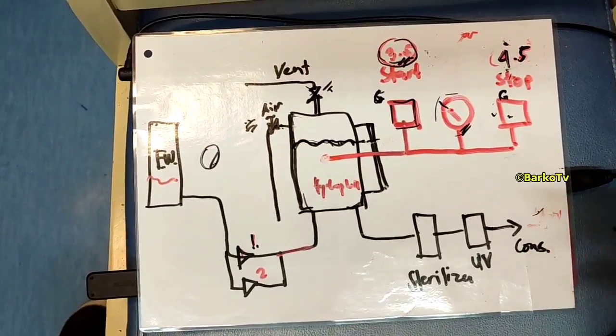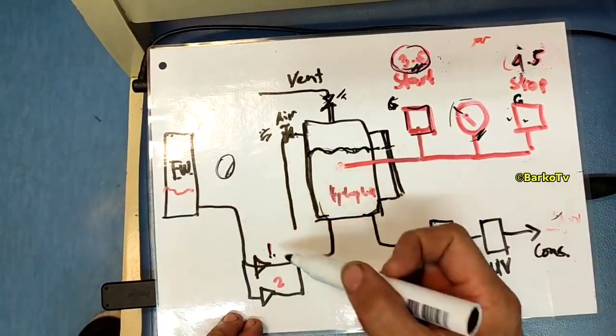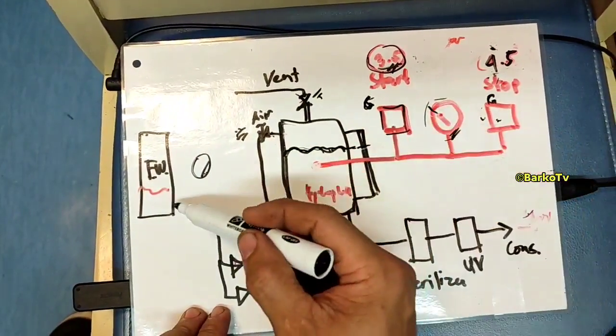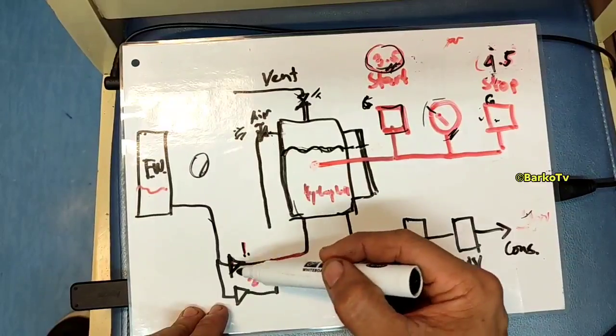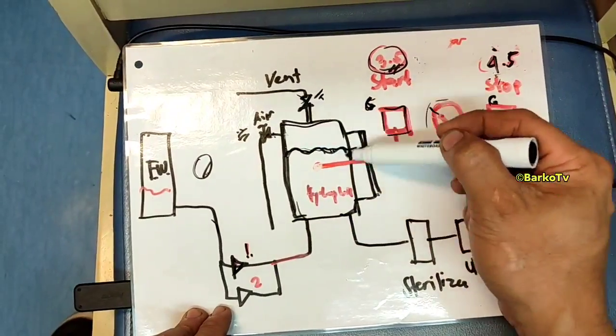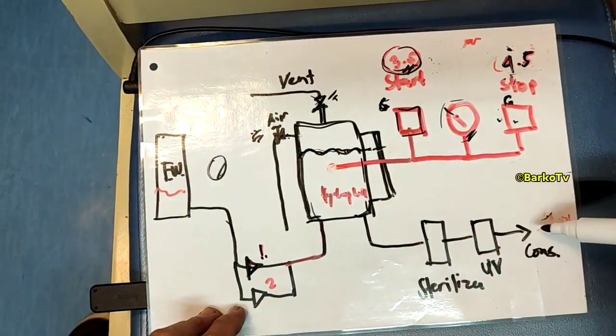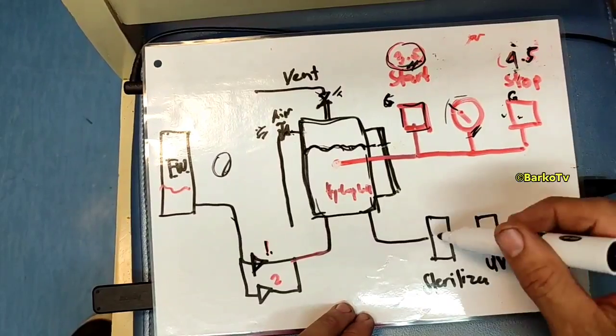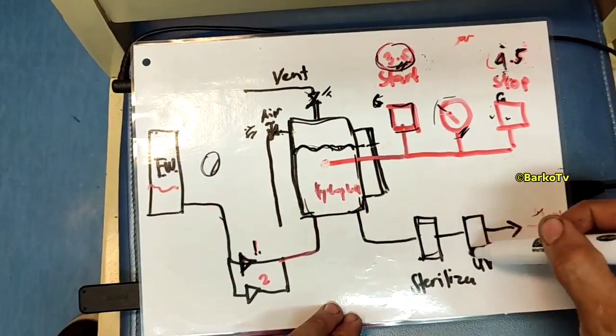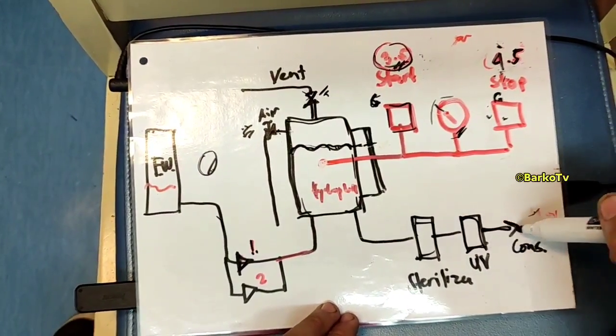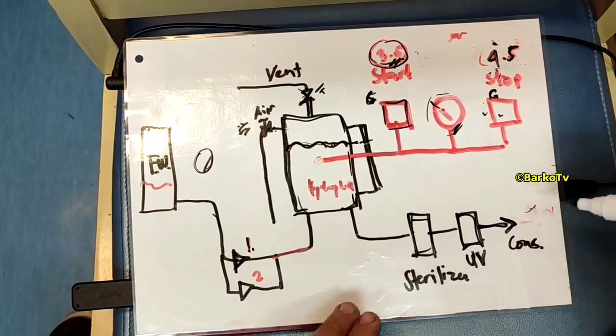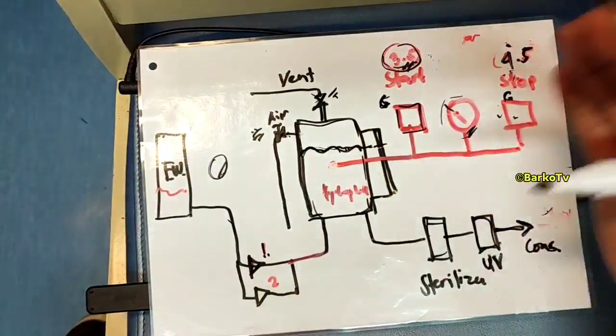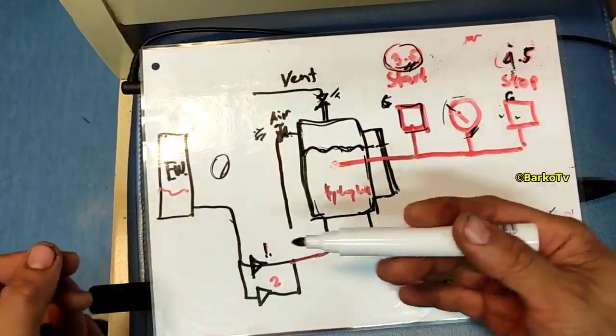Our topic is the hydrophore system. This is the fresh water diagram, located in the engine room. We have hydrophore fresh water with pump 1 and 2. The hydrophore supplies water to showers and deck accommodation, passing through a UV sterilizer, then for drinking or other purposes. We have two hydrophores — one for accommodation and one for technical use.